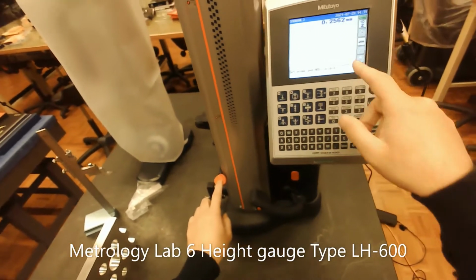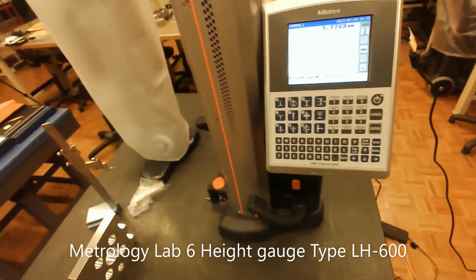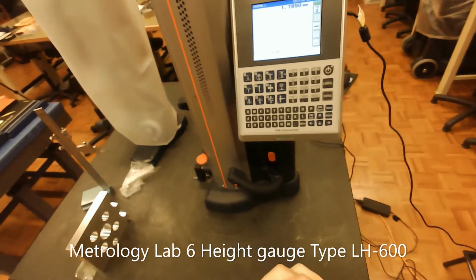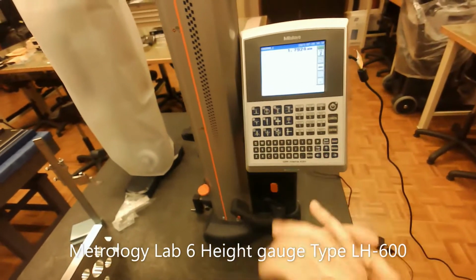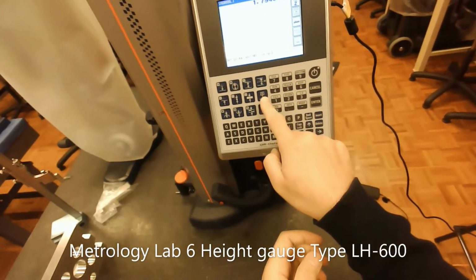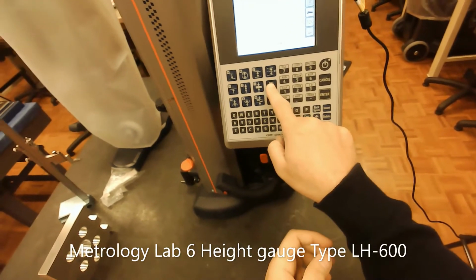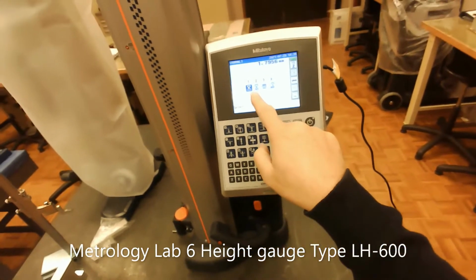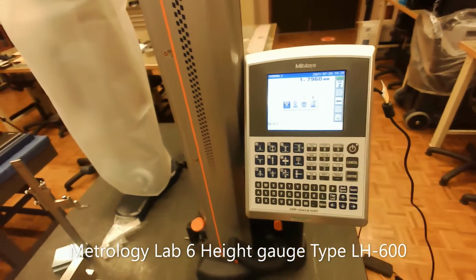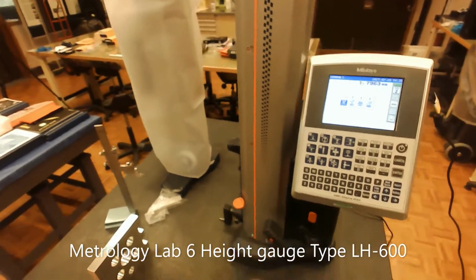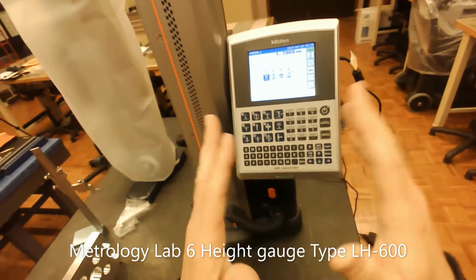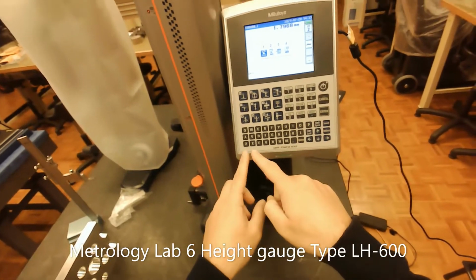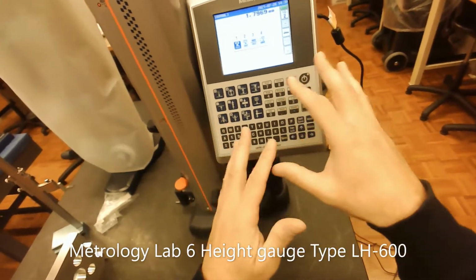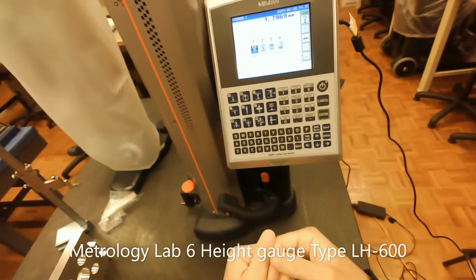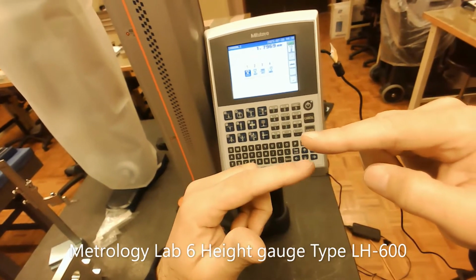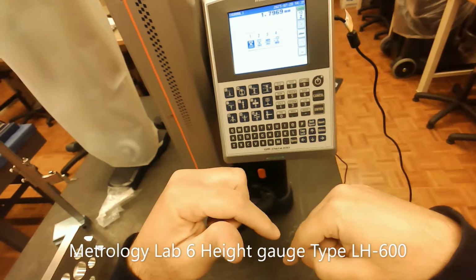Now the reading we're having here is, say, 0.05. I need to calibrate the device to set the origin. To do that, we have multiple options here. One of the buttons here says 0. So we set the 0 value. I'm going to press that, and I need to choose whether I'm going to use the absolute, the incremental, or absolute and incremental. Once again, to talk about the incremental and the absolute: absolute means that all the readings are referenced to the origin. The incremental is that the next reading is referenced to the present reading, and so on.